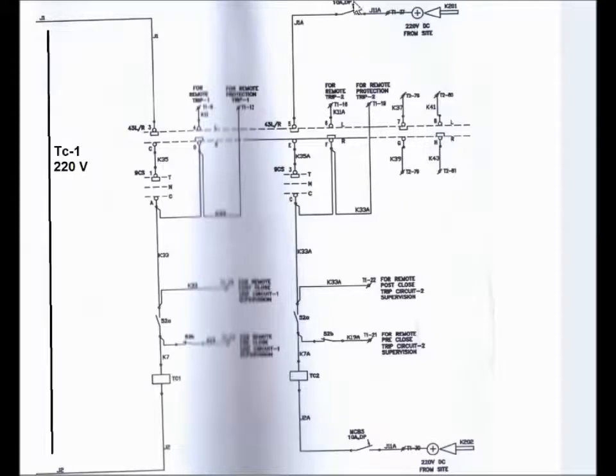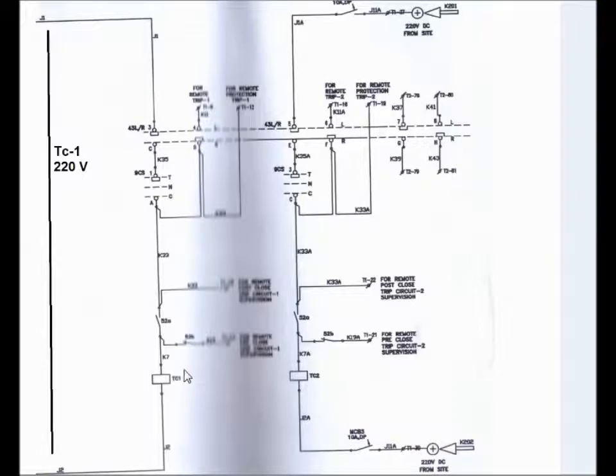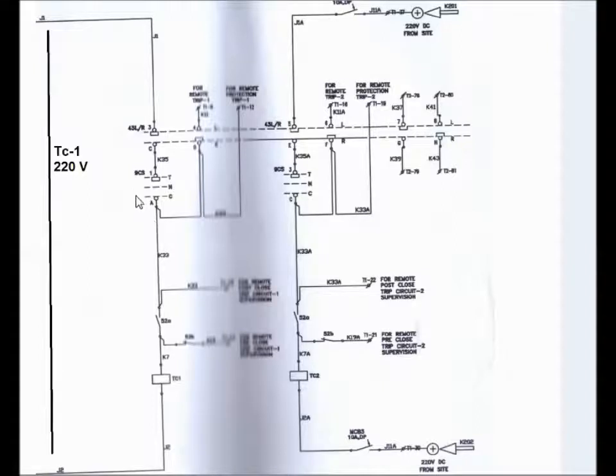There is another 10 ampere double pole MCB, and this MCB must be ON to connect the DC to the trip coil. For local tripping via TC1, the local-remote selector switch must be in local position. If we give the tripping pulse from the local control switch, the pulse will come to trip coil TC1 via the auxiliary contact of the circuit breaker.